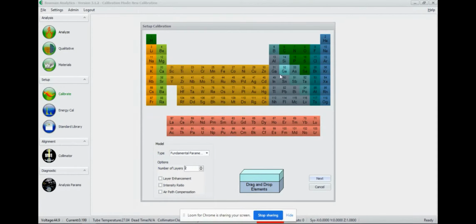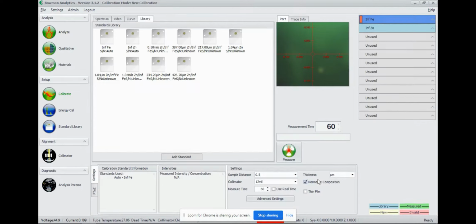And now we've got this nice little graphical representation of what our sample is. Now we come up here to our periodic table, grab whatever our element is that we want, in this case zinc. We're going to put that on top in our coating, and then our base layer is just steel. Obviously, a lot of times we say steel and we just mean iron. If you are using any kind of steel alloy, make sure you include those other elements in your substrate. We're going to hit next, and now it's going to come up to the actual calibration measurement screen.